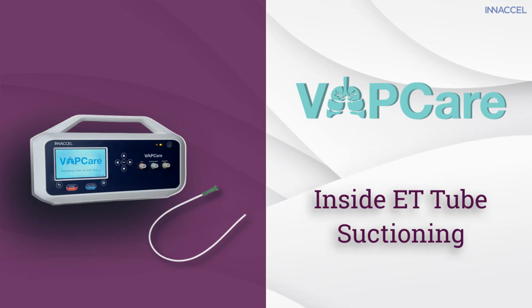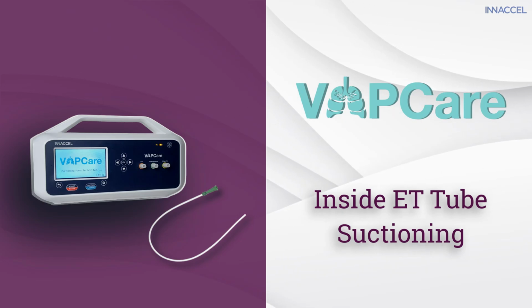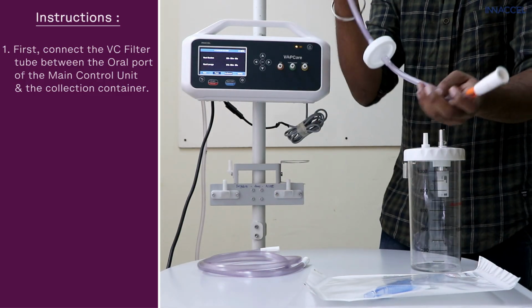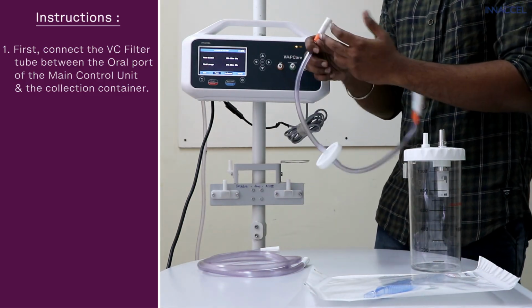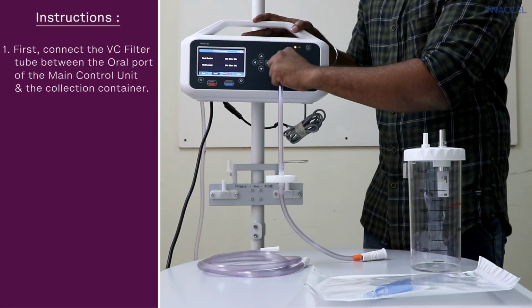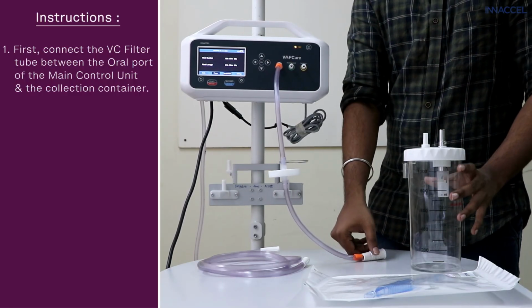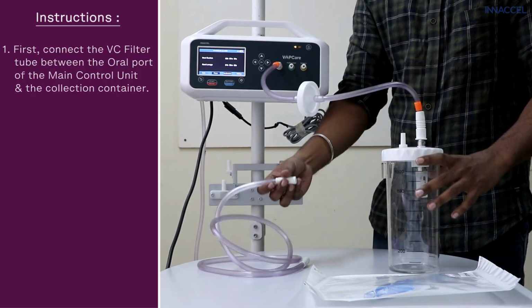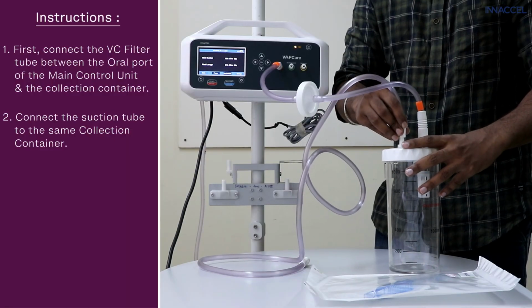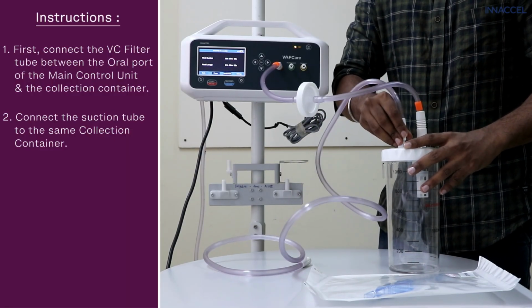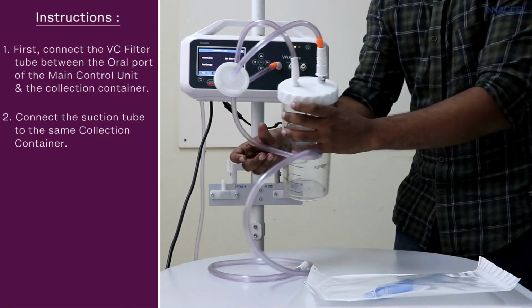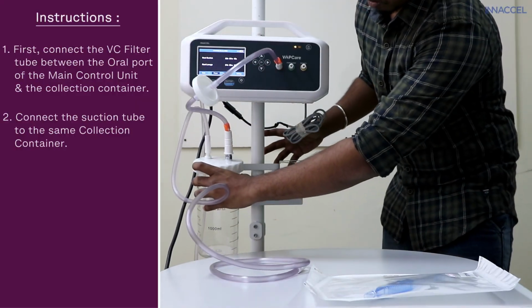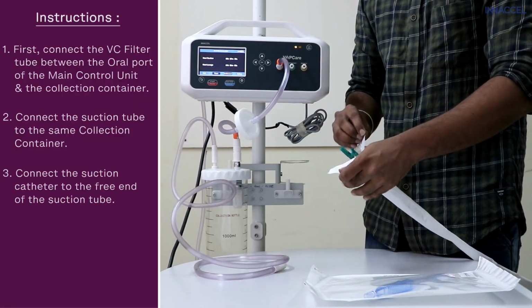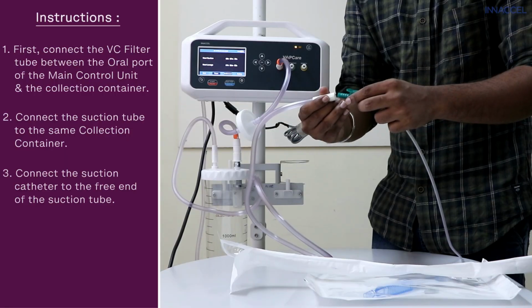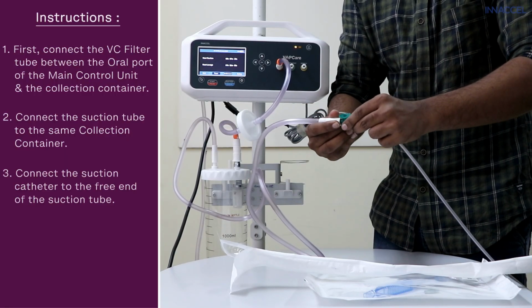To use VapCare for inside ET tube suctioning, the following steps must be performed. First, connect the VC filter tube between the oral port of the main control unit and the collection container. Connect the suction tube to the same collection container. And finally connect the suction catheter to the free end of the suction tube.